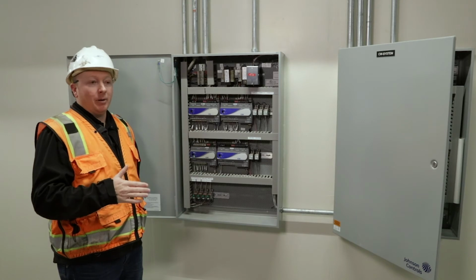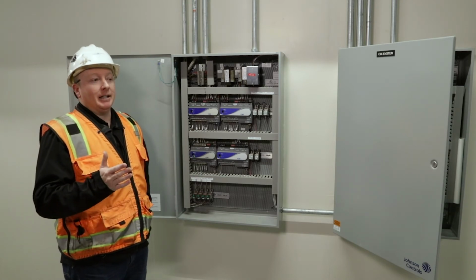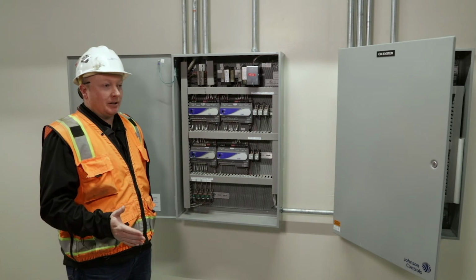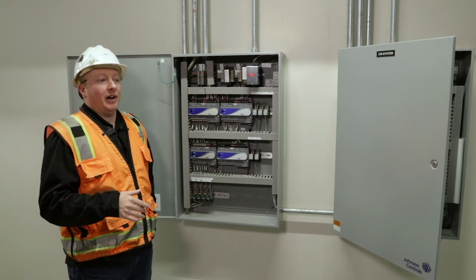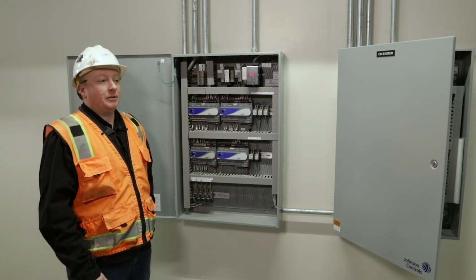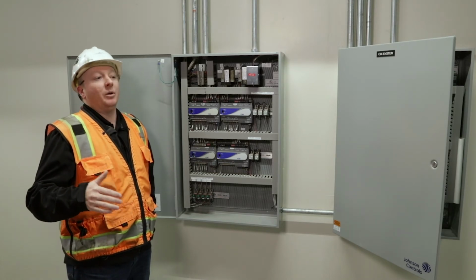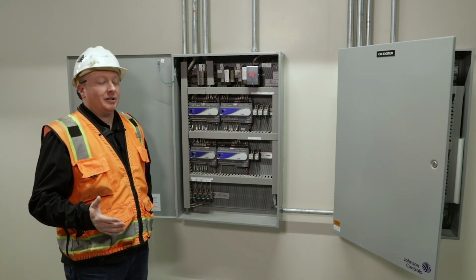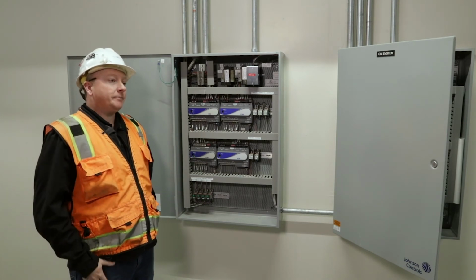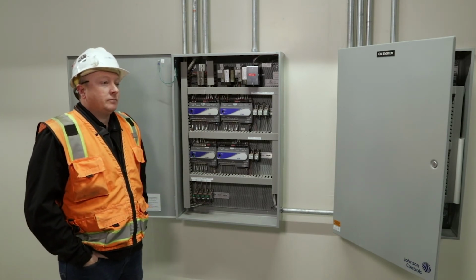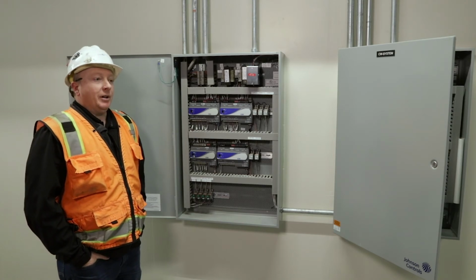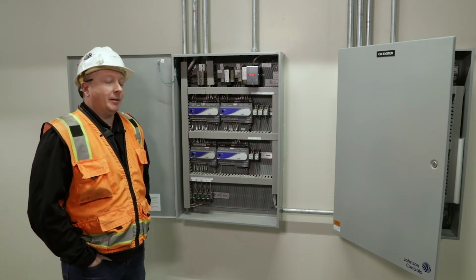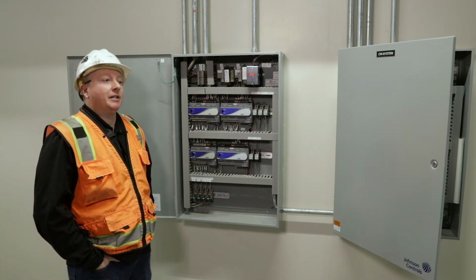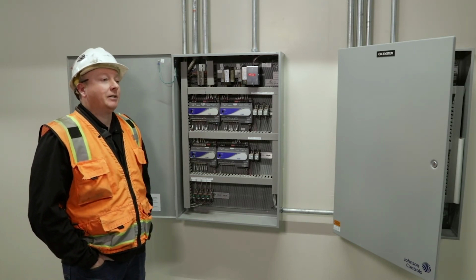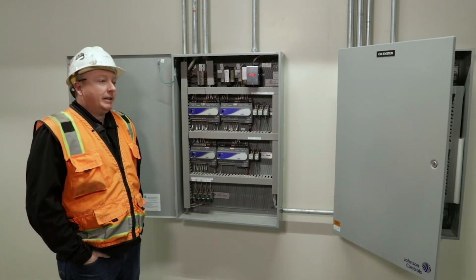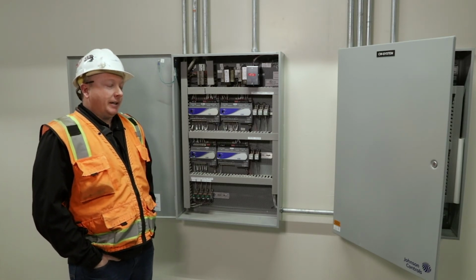So if we have one pump that gets to 100% and it can't get to whatever our DP set point is, it will stage on the second pump after 5 minutes and run 2 pumps in parallel to try to maintain. Once we achieve set point and the pumps get below 60%, I believe, we drop back off. The DP pressure set point auto adjusts on demand of what? No, it's going to be a fixed set point. I believe it's going to be right around 8 or 9 psi is what we were seeing last week. So I've got to confirm that with the balancer, but that should be where we land.